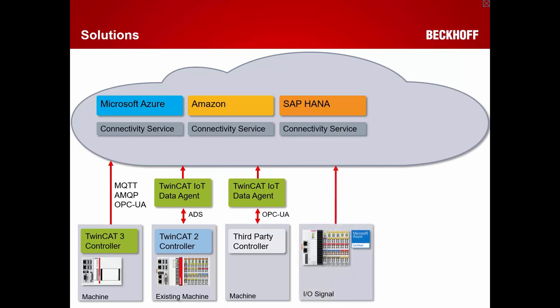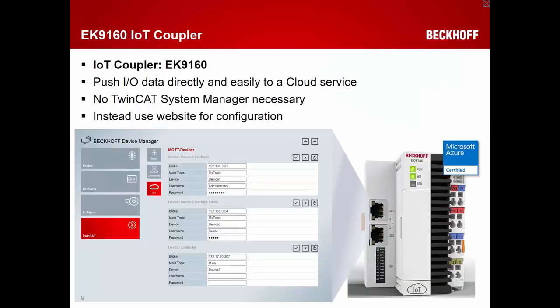Last year at the Hanover trade show, Beckhoff announced the IoT Coupler, the EK9160. It's a plain hardware device with no TwinCat on board, configured entirely via a built-in website — similar to a DSL router interface. On the EK9160, you can configure message brokers to communicate with, including the Microsoft Azure IoT Hub. This device is also Microsoft Azure certified.